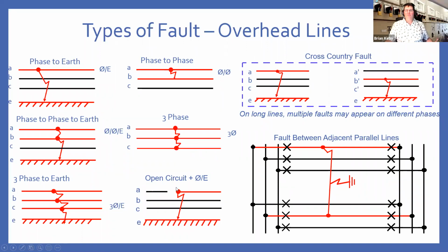And also, I've mentioned broken conductor. You may have a broken conductor which earths one phase, but the line past the break is de-energized. So these are all typical conditions you may see on UK transmission lines, but they are, as I've mentioned previously, quite rare. They don't happen that often.